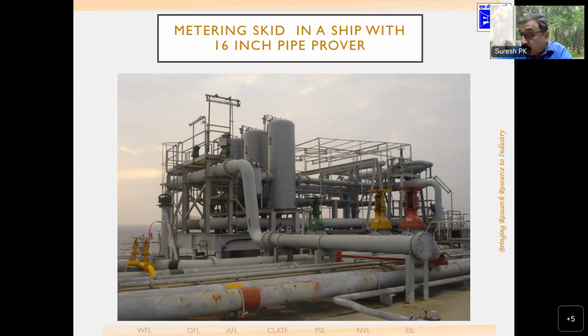Temperature of the fluid may not affect the meter as such, only the measurement it can affect. The meter will not be affected, because the temperature variation is too low. If you are using it at 20 degrees centigrade and 100 degrees centigrade and calibrating it at minus 15, then it may affect, but otherwise it will not. Okay, sir, thank you.